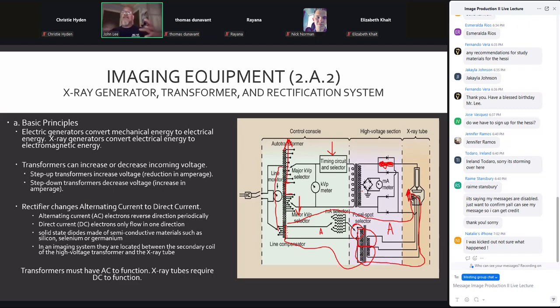Now, since the magnetic field opens and closes a certain way, the electrons on the secondary side are going to move back and forth just like they were in the primary coil. All right. So still alternating current. Not good for our X-ray tube. So in this area, we have our rectification circuit made up of these diodes. Now, the diodes allow for electrons to flow in one direction and only in one direction.